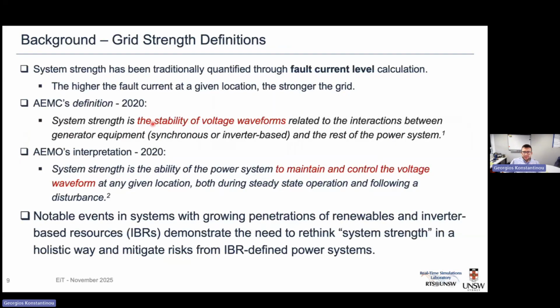Now, from an analysis point of view, traditionally system strength has been quantified through fault current level calculations. So it was a relatively straightforward procedure of looking at your network, trying to understand the states of the network, heavy loading conditions, low loading conditions, how much synchronous generation you would have available at a particular point in time, the interconnections, the lines that you have available, and then calculating the fault levels at the different buses.